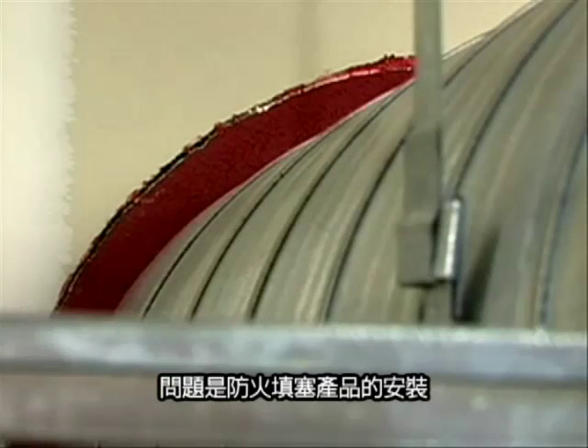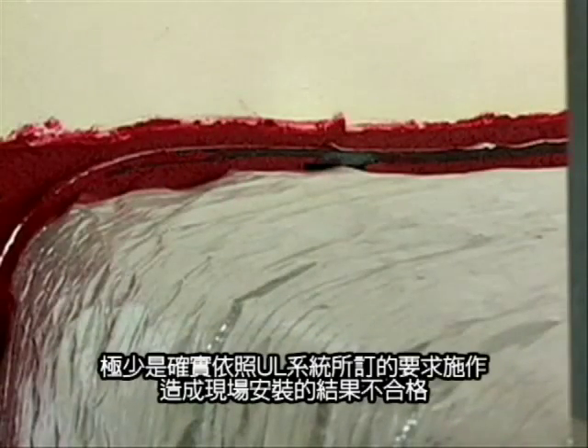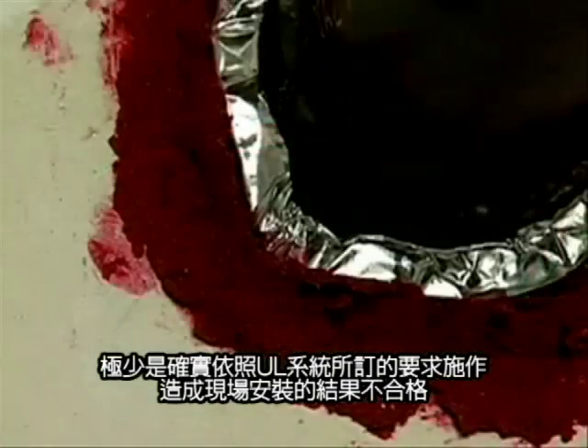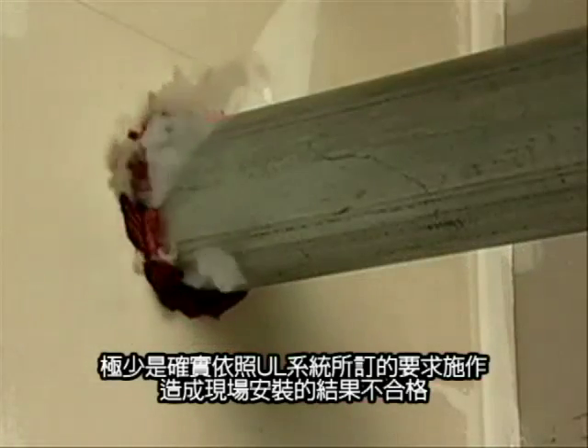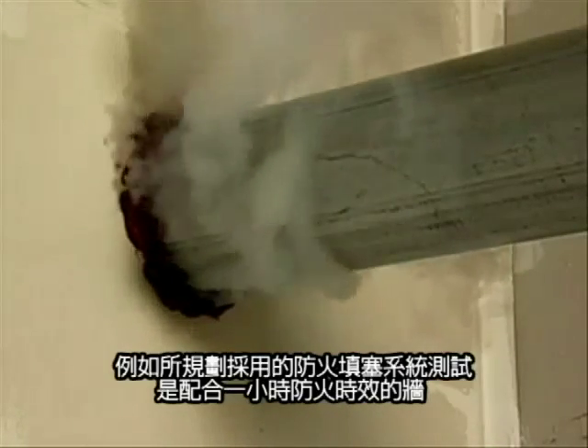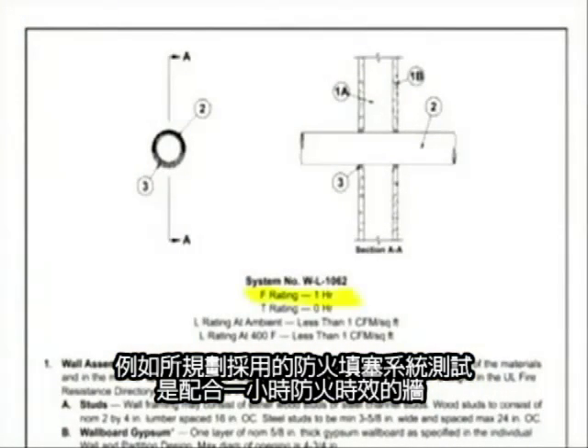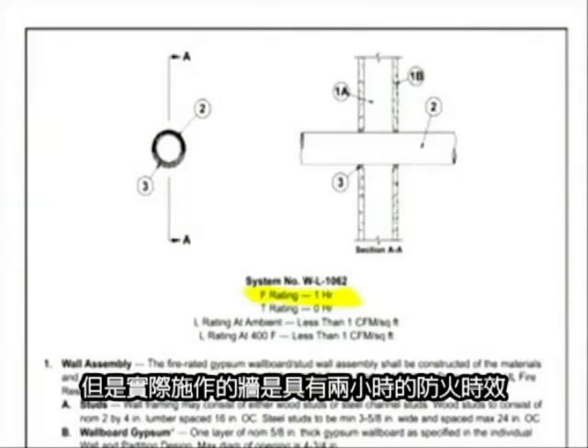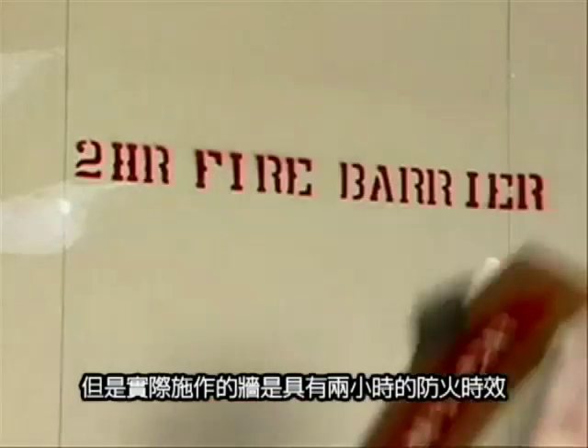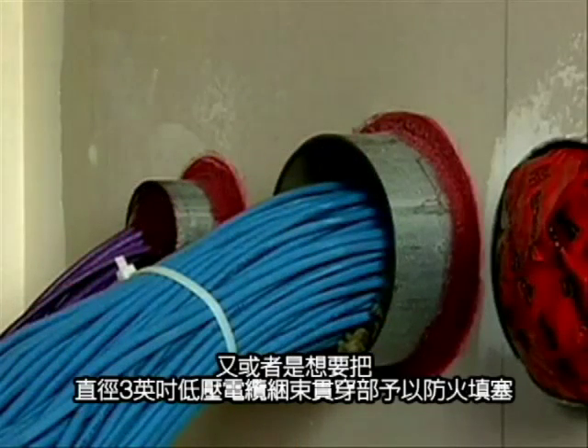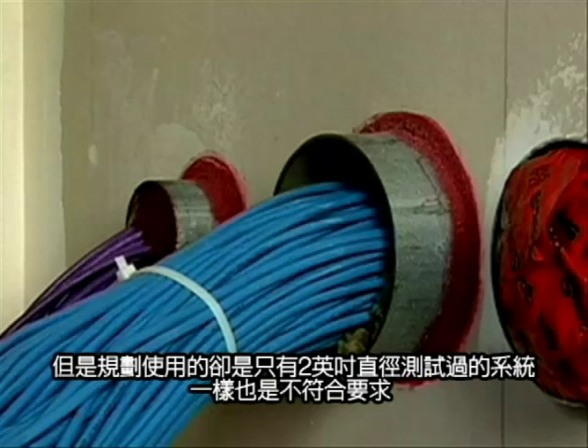The problem is that fire stop is rarely installed exactly as mandated in the requirements of a UL system, which makes the installation non-compliant. For example, maybe the system that you're planning to use is tested only for a 1-hour wall, but your wall has a 2-hour rating. Unintentionally, installing this system would reduce the rating of the entire wall to 1 hour. Or perhaps you want to fire stop a 3-inch diameter bundle of low voltage cables, but the system you're planning to use is tested only up to 2-inch in diameter, which would also be non-compliant.